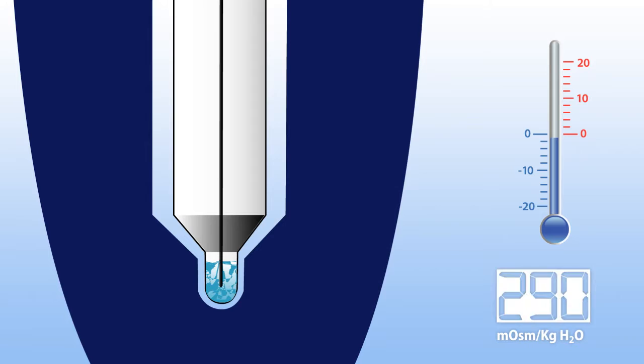The osmometer precisely measures this temperature at the plateau and calculates the concentration in milliosmoles per kilogram of water. This is the test result reported by the osmometer.